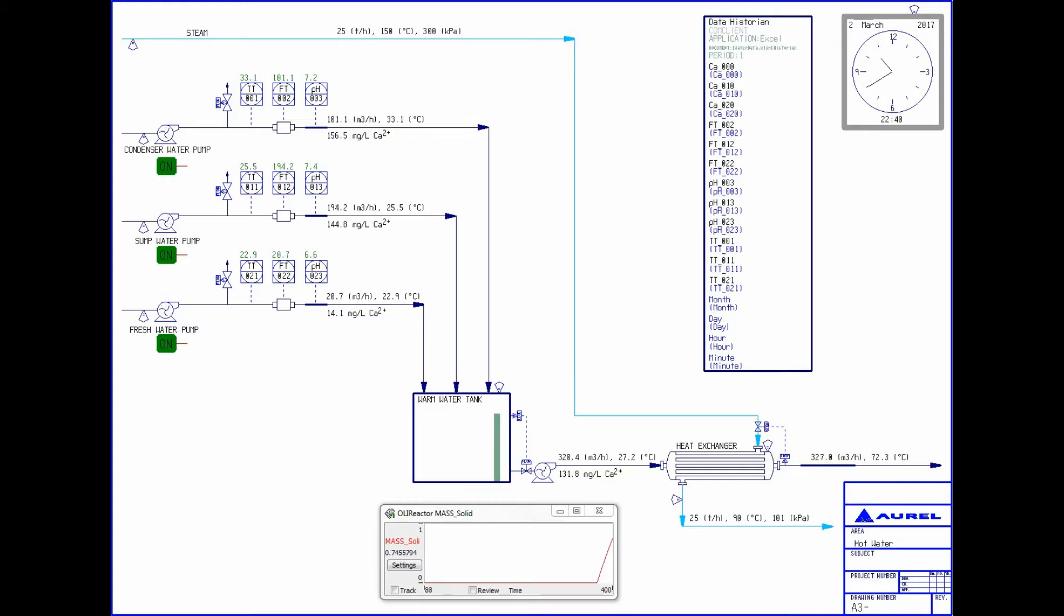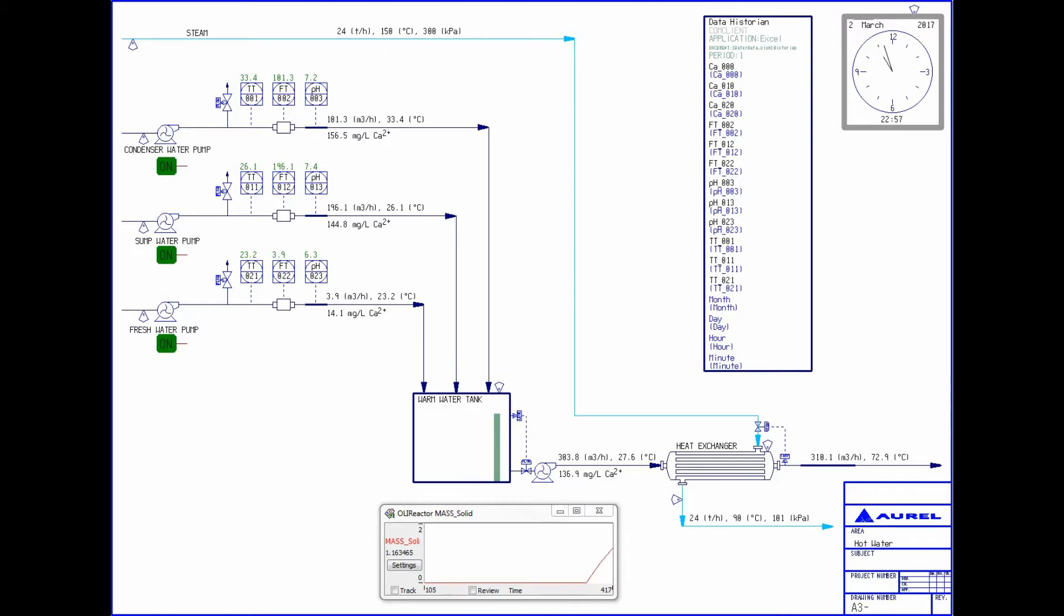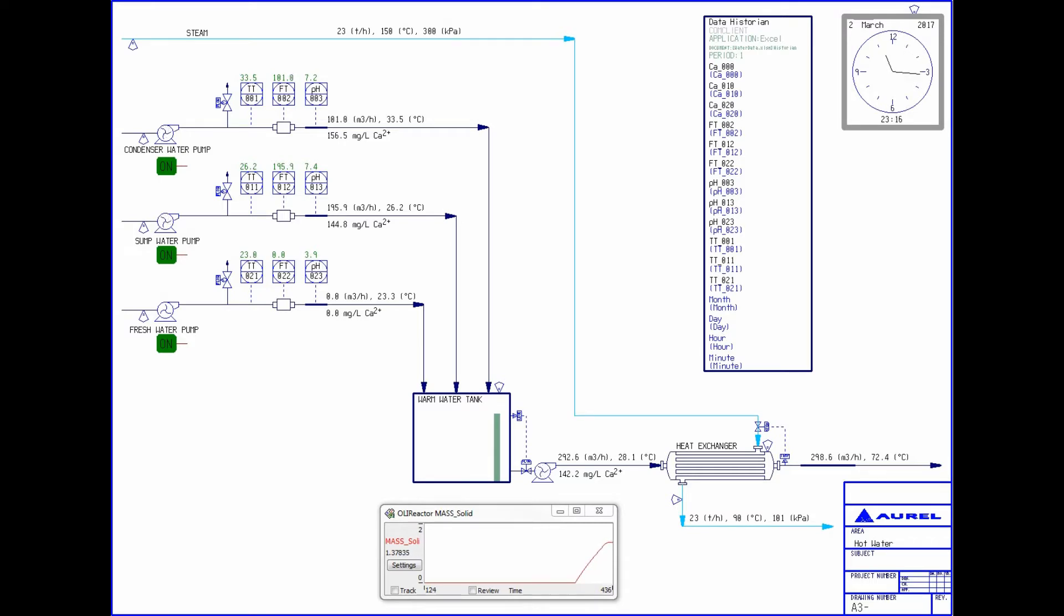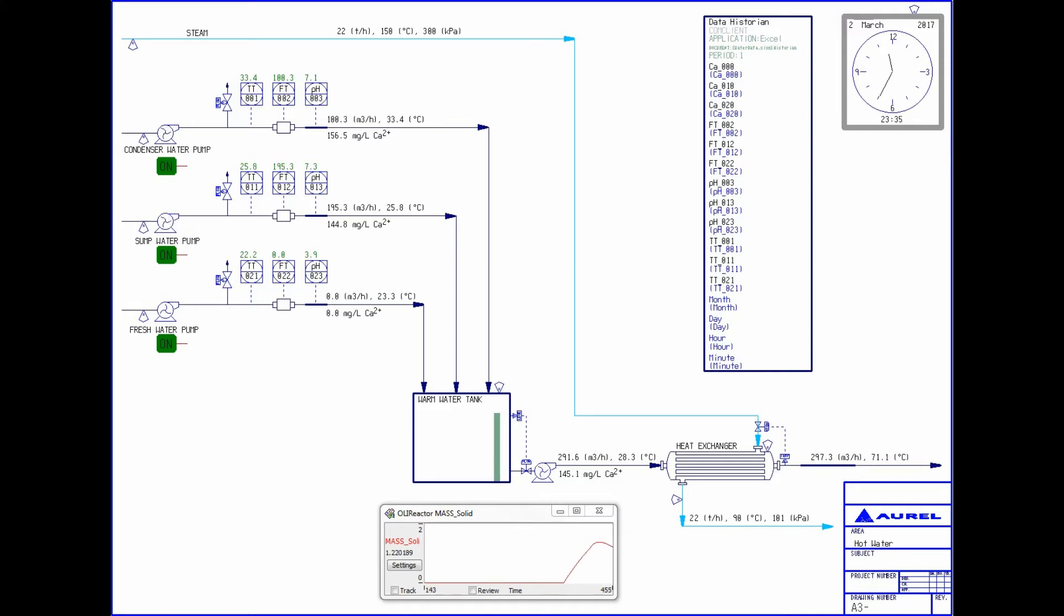When the simulation is run, we can see our three water streams are changing as the Excel sheet is being communicated with. We can now use OLI to predict if scaling may have occurred in the heat exchanger while accounting for the dynamics in the process. This can be taken a step beyond a COM link and directly connect CADSIM to a DCS server through an OPC connection. In this way, you could run a simulation alongside your actual process with live data being fed into CADSIM and OLI.